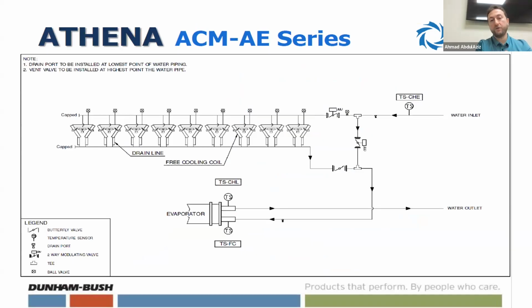This is the free cooling diagram. In ACM, we utilize an integrated coil. It's not just an additional coil added to the chiller, the same as what Tom presented in the scroll type, where you have an extra V coil with fan and the expansion tank. In ACM, we utilize the same DX coil. If you consider this is your DX coil, the condenser, we add another coil here for the free cooling. So you save the space.